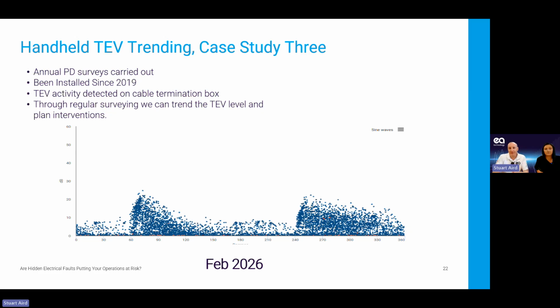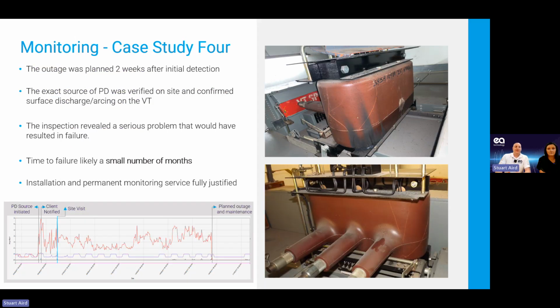So I've got a few case studies now that demonstrate how permanent monitoring can pick up these things straight away, and we can act on them as quickly as possible. This one here is a substation, and we were putting a monitor in mainly for trending. We're watching high level transient earth voltage activity within CTs in this substation, and that's why the system was there. But whilst putting a system in, we've got VTs that are mounted on the top of the switchboard, so they're mounted horizontally, racked in, and they give us our low voltages inside the substation. So in this case, we put some ultrasonic microphones pointing at the VT as well.